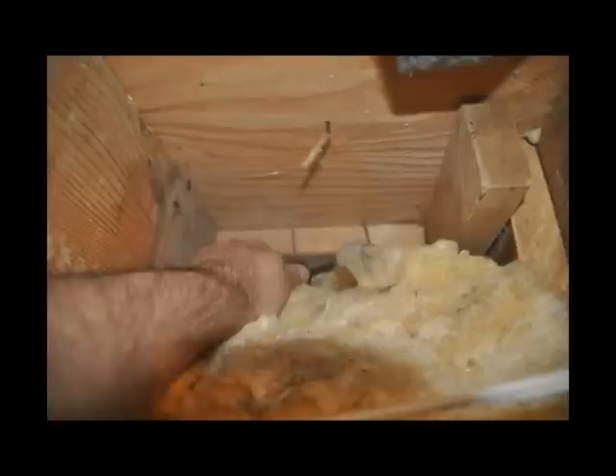The residential investigator went down to the basement and removed some of the insulation that was hiding these two column foundation cavities. He stuck his camera into these hidden cavities and took photos. The photos showed that these areas were moist, cold, and condensation was occurring, permitting musty odors, mold, and deterioration to joists and timbers.